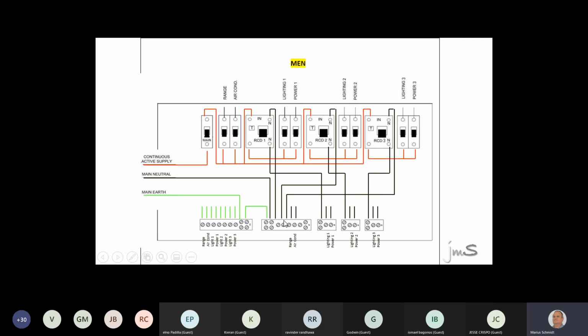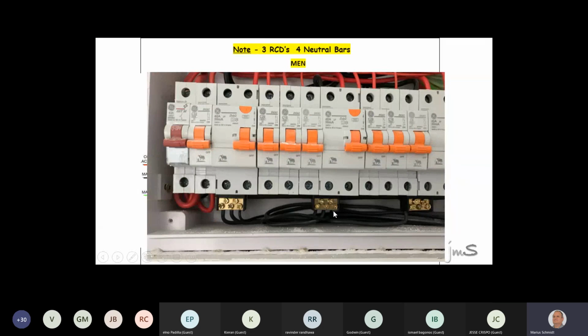Happy with that? So guys, when I ask you a question about switchboards, think practically what you will do. All right? Happy with that? Right. 3 RCDs, 4 neutrals. Now I'm going to zoom in. See that neutral bar? I'm going to zoom in. Is that what you guys talked about? Yes. That is also a neutral bar. But 3000 says the reason I put 1 neutral per each one is because when you remove a neutral, you do not disturb others. Each one has got its own neutral conductor.